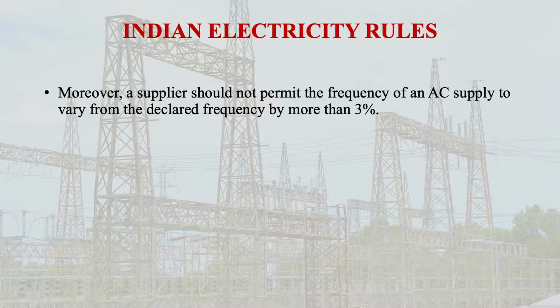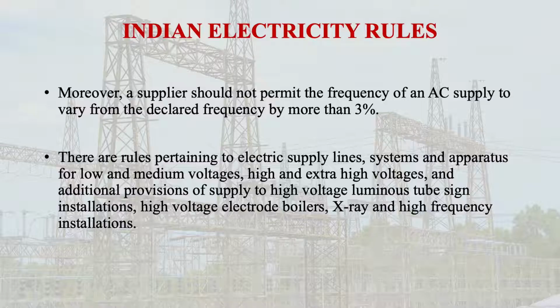Moreover, a supplier should not permit the frequency of AC supply to vary from the declared frequency by more than 3%. So only a variation up to 3% is possible as per the rule. That means, suppose 50 Hertz, the permitted variation is 1.5 Hertz. That means 48.5 Hertz on the lower side. Similarly, it can be on the higher side. So the variation should not be more than 3% in case of frequency.